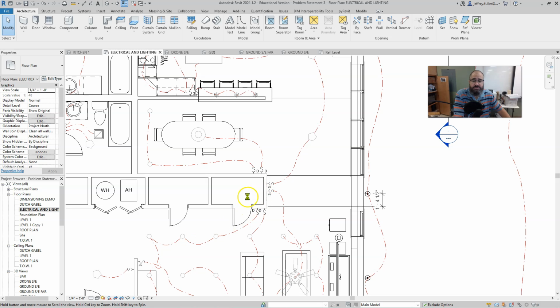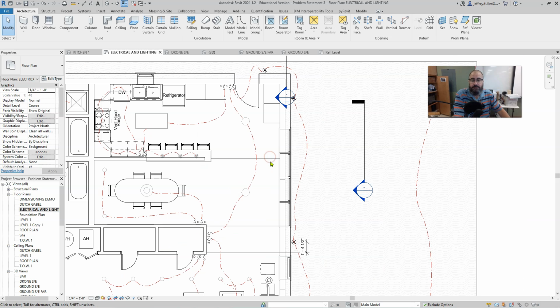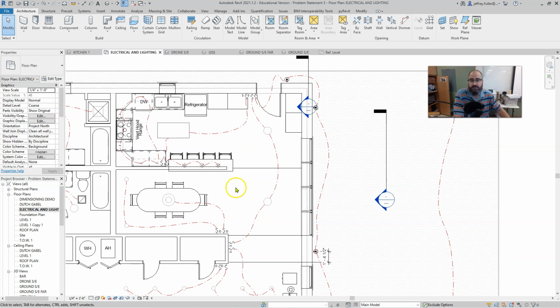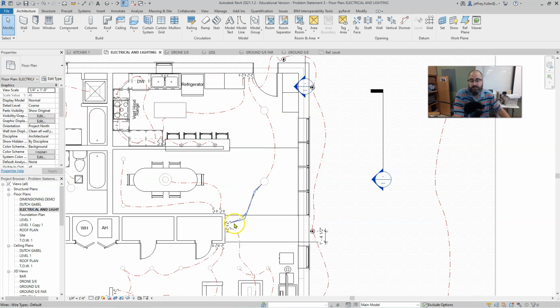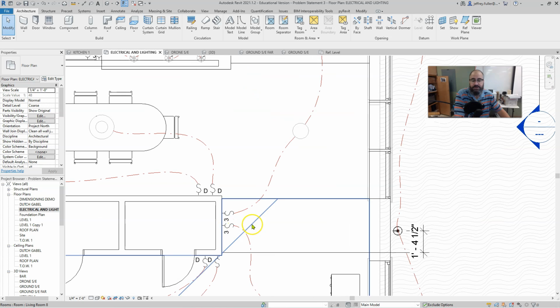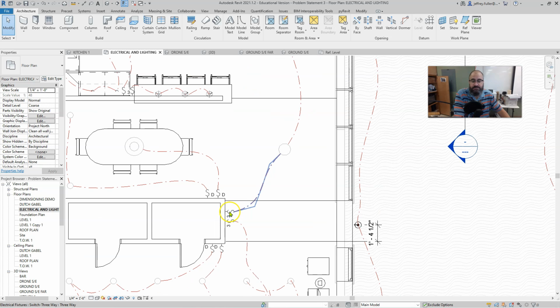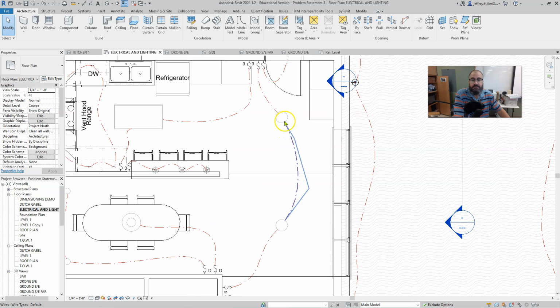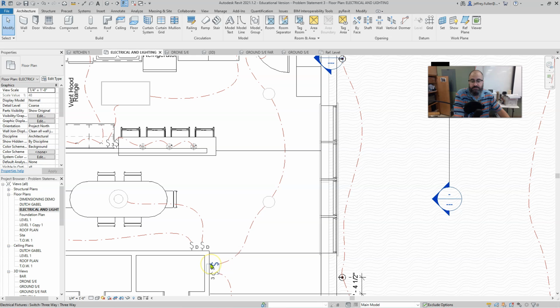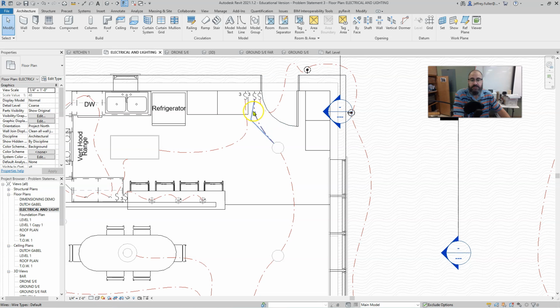And you can also see my switch placements. I put some thought into convenience for the placements of those switches, and where they would want to turn those things on and off. And I use that also when it comes to three-way switches. Now, this is a three-way switch, and this one, for instance, can control this light fixture and this light fixture up here from two locations. This is the second location. So when you're running three-way, it's from the switch to the fixture and then to every other fixture that it controls and then to the second switch.